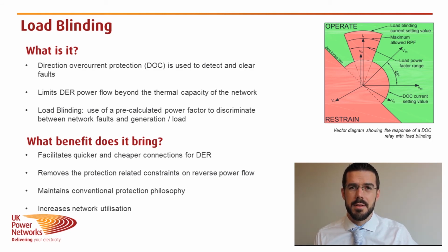It can also limit the amount of generation that we can have connected, as if there is too much generation, it could cause a high enough power flow to trip the directional overcurrent protection.